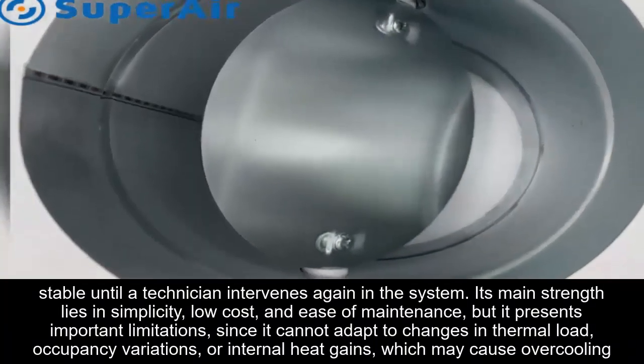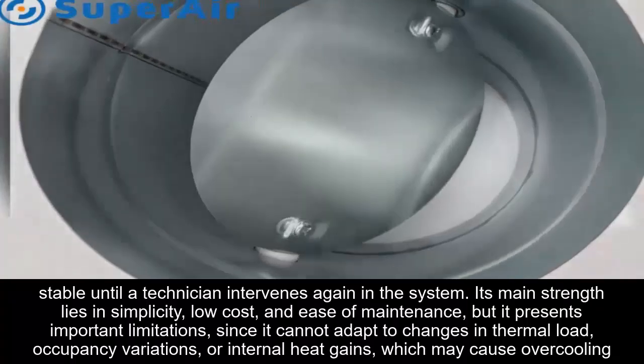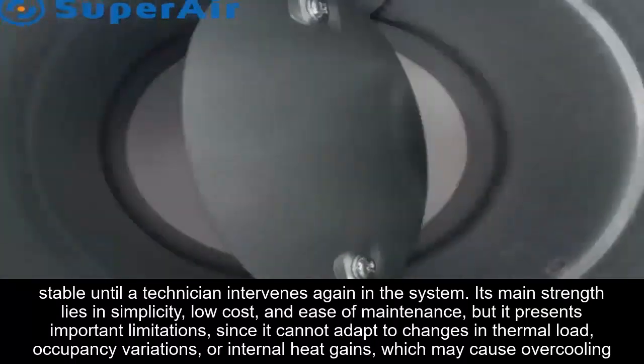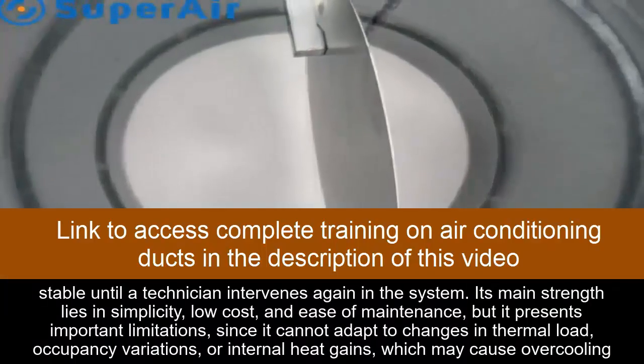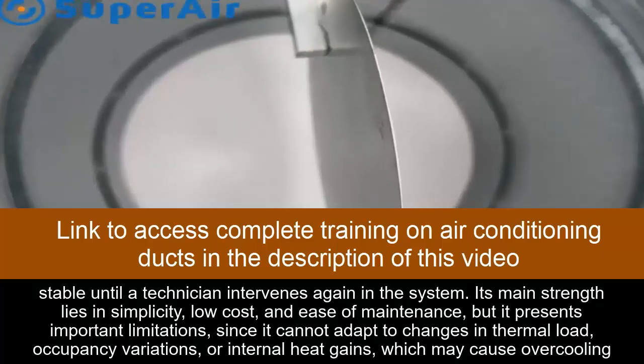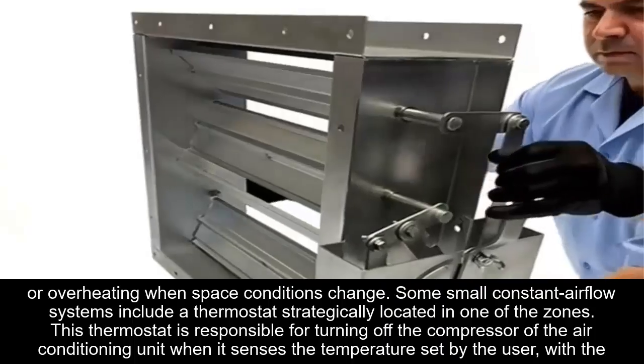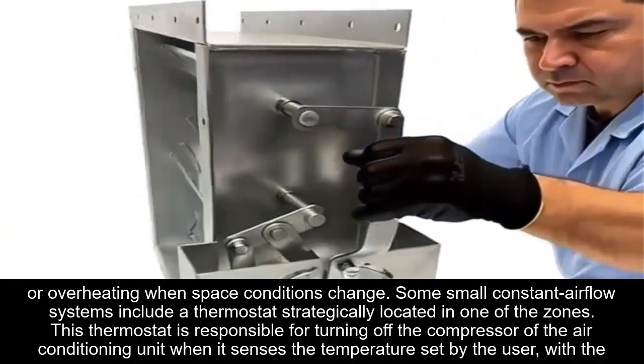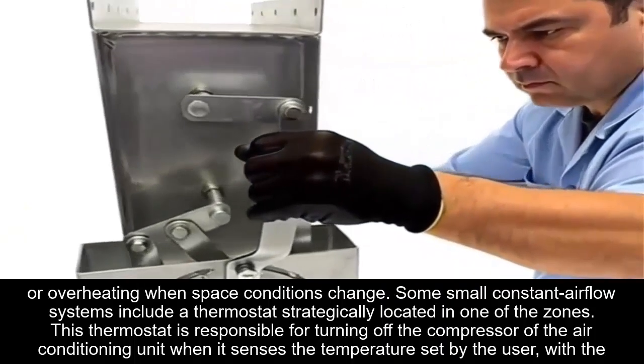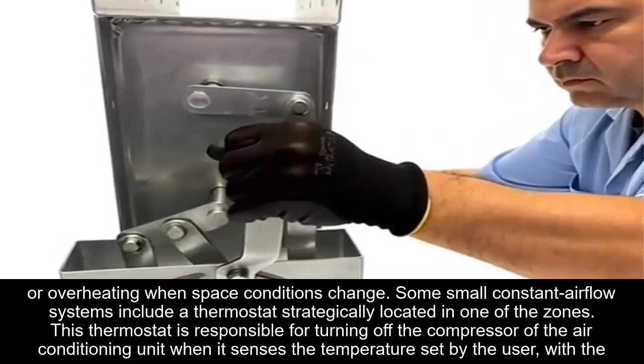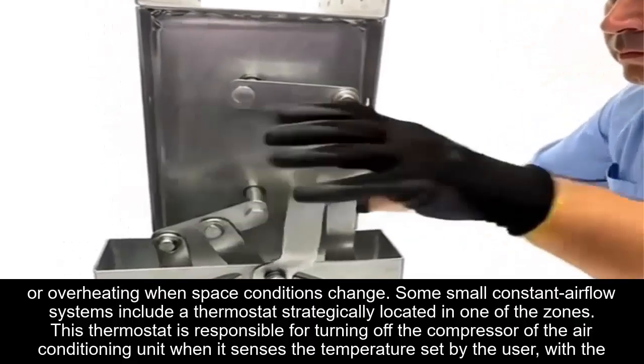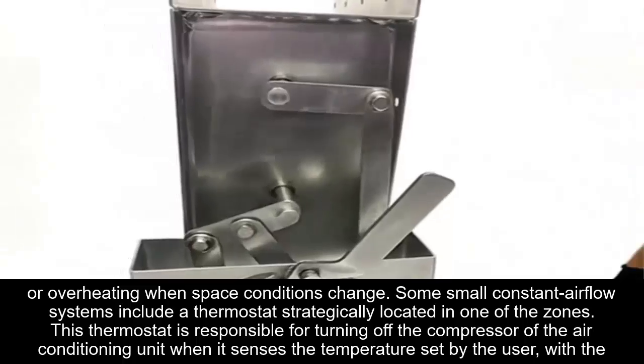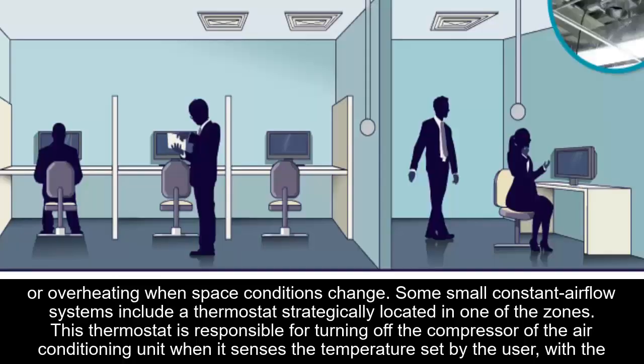Its main strength lies in simplicity, low cost, and ease of maintenance, but it presents important limitations since it cannot adapt to changes in thermal load, occupancy variations, or internal heat gains, which may cause overcooling or overheating when space conditions change. Some small constant airflow systems include a thermostat strategically located in one of the zones.